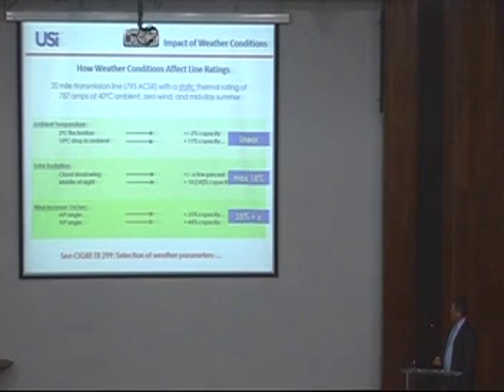For many details, you can look at the CIGRE technical brochure 299, which describes in great detail the impact of all ambient conditions, titled "A Selection of Weather Parameters for Bare Overhead Conductor Ratings." If you don't have it, Carlos has access to that. So that means if you want to do DLR, the wind has the biggest cooling impact on the conductor. The problem is the wind is exactly the parameter which varies the most in time and in space, especially for the critical wind speeds, the low wind speeds. So how do we deal with that?